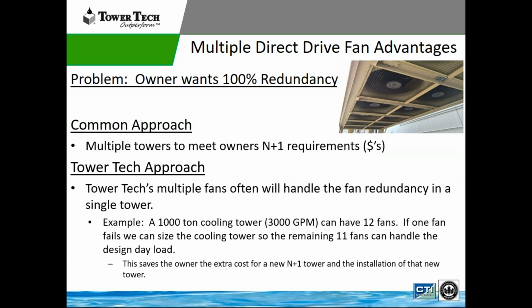So the problem is the owner wants 100% redundancy. The common approach with multiple towers is, in order to meet that 100% redundancy, if that fan goes down, we need another cooling tower active. So that means you're buying another cooling tower in order to meet your N+1 requirement.